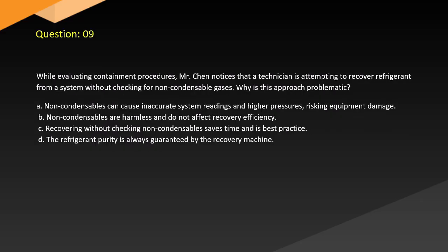Question 9. While evaluating containment procedures, Mr. Chen notices that a technician is attempting to recover refrigerant from a system without checking for non-condensable gases. Why is this approach problematic? A. Non-condensables can cause inaccurate system readings and higher pressures, risking equipment damage. B. Non-condensables are harmless and do not affect recovery efficiency. C. Recovering without checking non-condensables saves time and is best practice. D. The refrigerant purity is always guaranteed by the recovery machine.